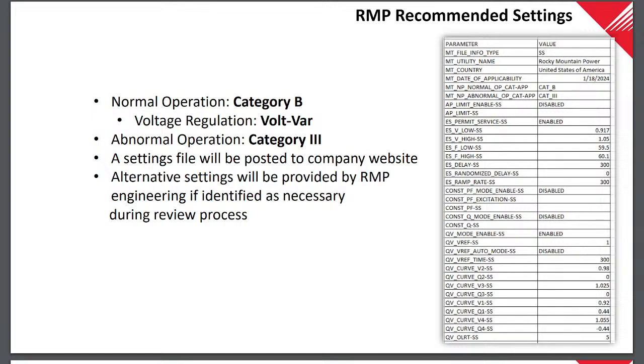So the first one, as we talked about on that first slide, was normal operation, where you either had category A or category B. Category B is a setting that allows for all of the regulation options. Even though category A covers volt-VAR, we want the ability to go to volt-watt if volt-VAR isn't enough, and volt-watt is a category B setting.